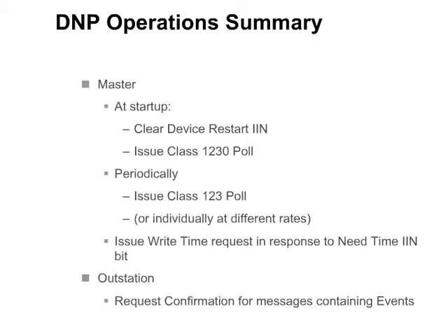Periodically after that, the master issues Class 1, 2, and 3 event polls, either together or individually at different rates. If the outstation sets its need-time IIN bit, then the master should issue a write-time request. And the outstation should request confirmation for any messages that contain events.